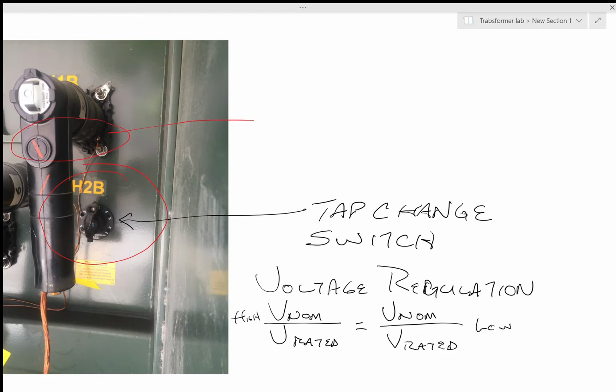If anybody works for ICT or works over at the Undergraduate Learning Center, I know a couple people over there are always complaining about low voltage in the summer. We could go over there and tap it one so that we could up the voltage, and it depends on the nameplate and what the tap ratings are and all that stuff. But you just turn the transformer off, pull this tap change switch out, turn it to the next one, and you'll get, depending on which way you want to go, high voltage or low voltage, depending on what's coming in and what you want coming out.